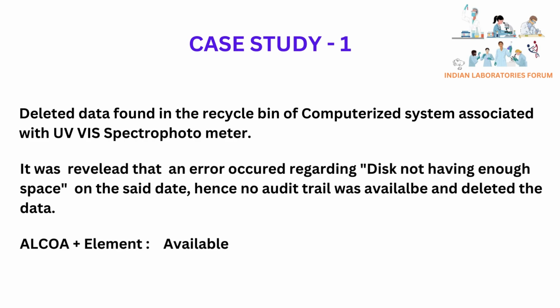Case studies help in better understanding of data integrity issues. Case study 1: deleted data found in the recycle bin of the computerized system associated with a UV visible spectrophotometer. During the investigation, it was revealed that an error occurred regarding the disk not having enough space on the said date. Hence no audit trail was available and the data was deleted. This is non-compliance to the ALCOA principle, as the data which was deleted intentionally is not available.